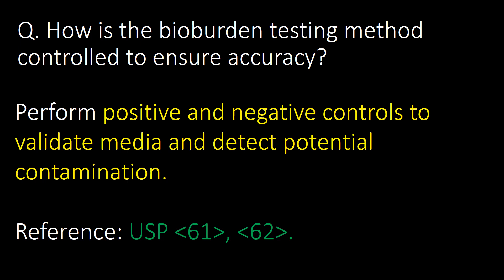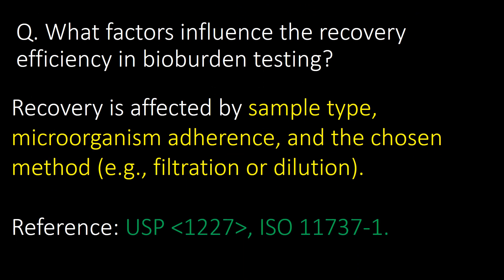How is the bioburden testing method controlled to ensure accuracy? Perform positive and negative controls to validate media and detect potential contamination. Reference USP Chapters 61 and 62. What factors influence recovery efficiency in bioburden testing? Recovery is affected by sample type, microorganism adherence, and the chosen method — for example, filtration or dilution. Reference USP Chapter 1227 and ISO 11737-1.